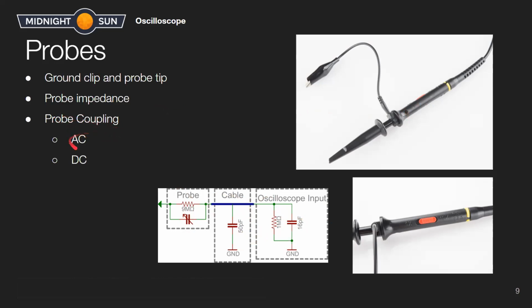So there's also different probe coupling options. I believe this is also in that same probe setup menu that I was telling you about. The two basic ones are AC coupling and DC coupling. AC coupling just means that alternating current will be displayed, and DC coupling just shows the signal with the DC component included. I think usually you just make a measurement with DC coupling. The other thing to know is that these are just passive probes. So if you're measuring very high frequency signals, you would need a higher quality probe with active amplifiers and things. So these will generally just be used for relatively low frequency applications.